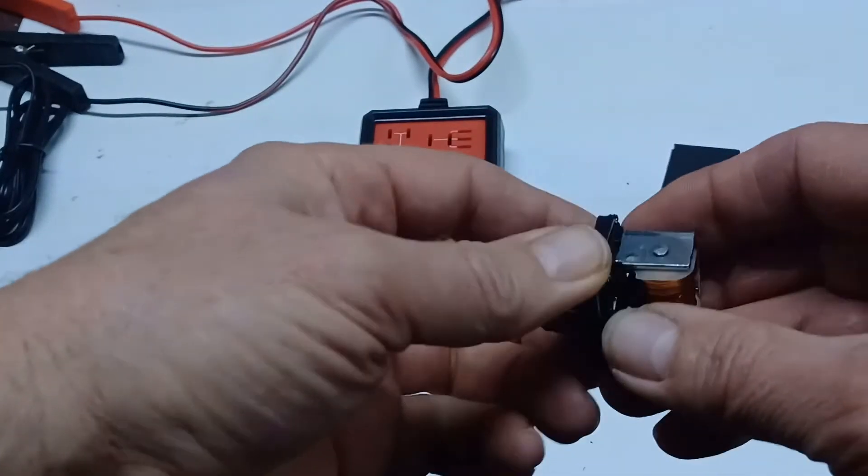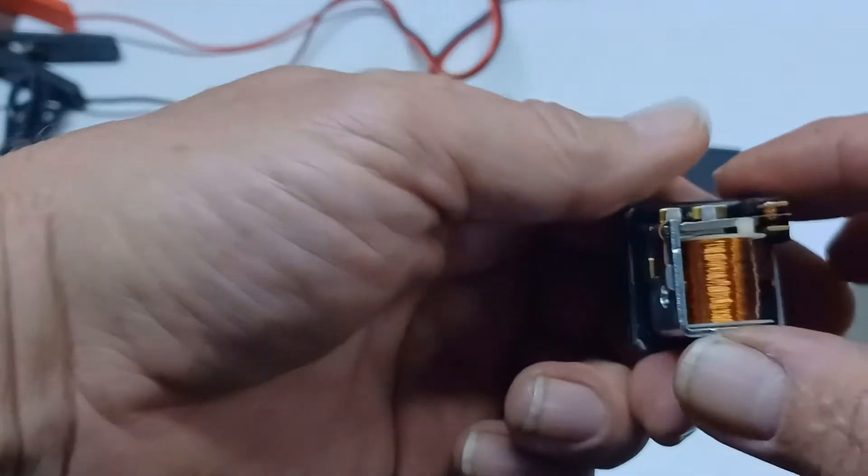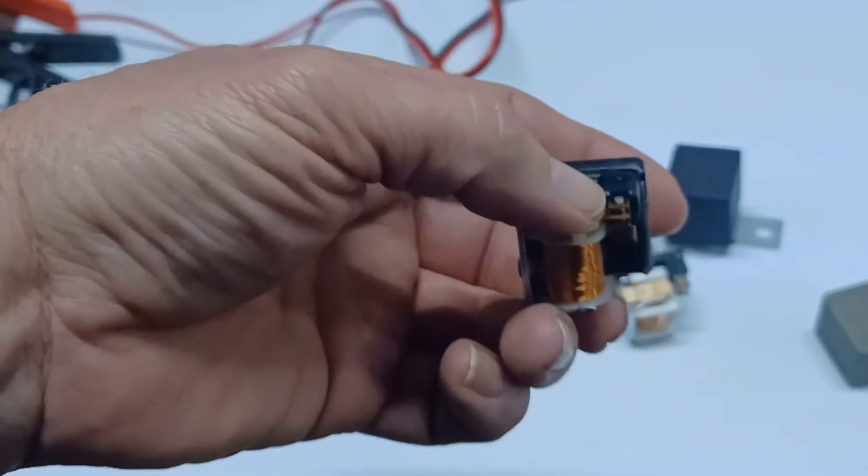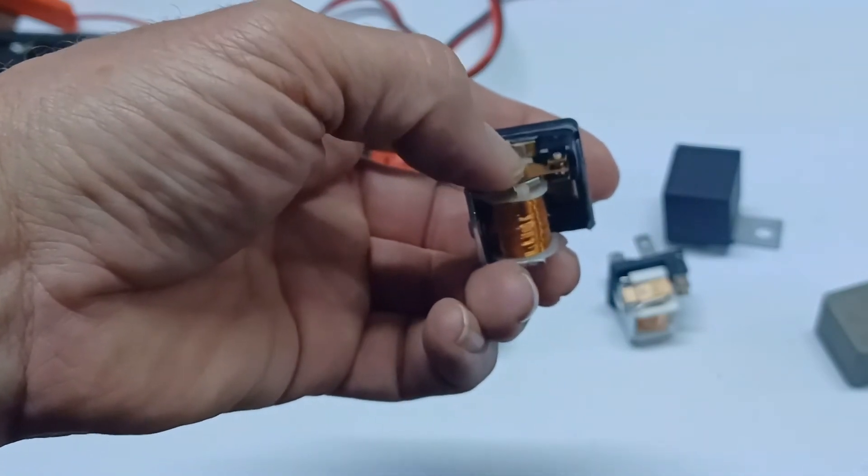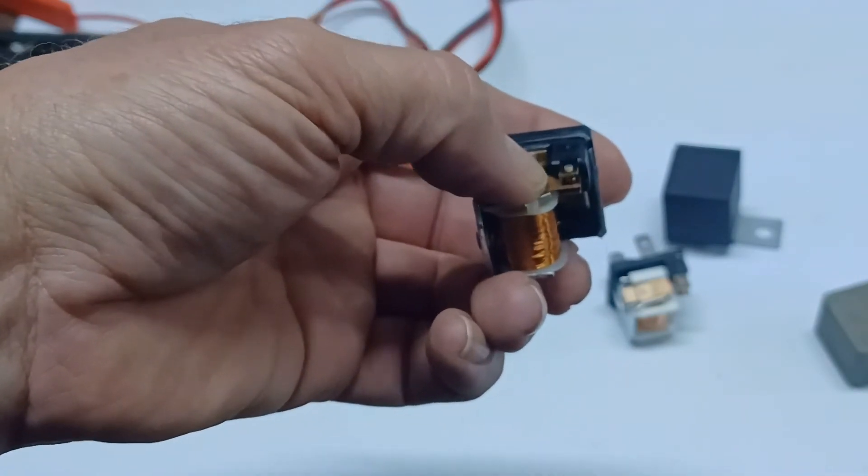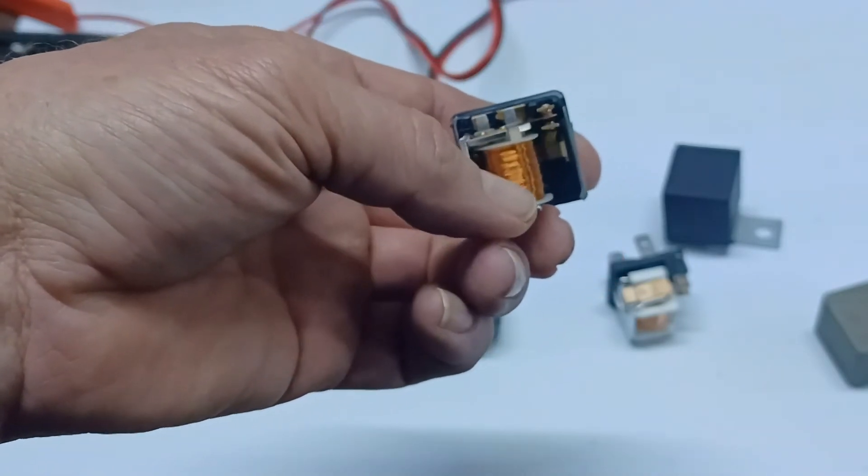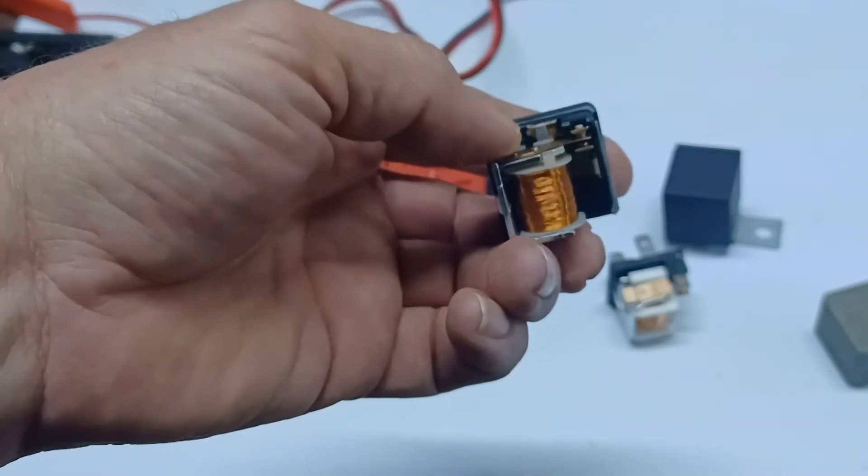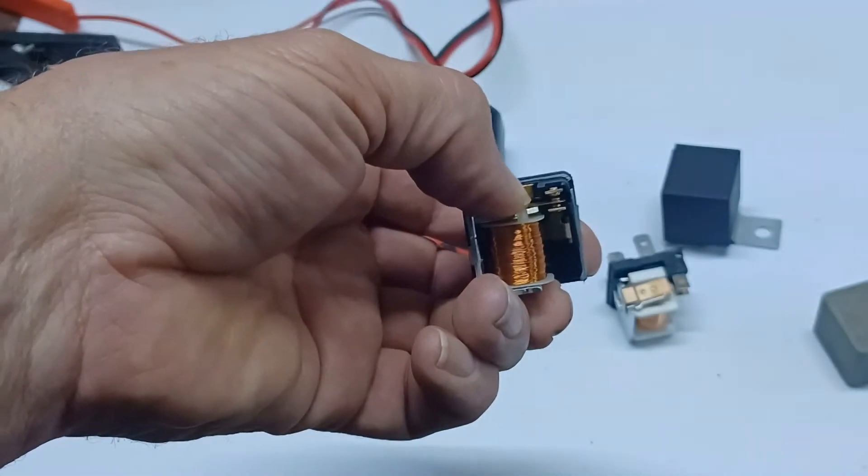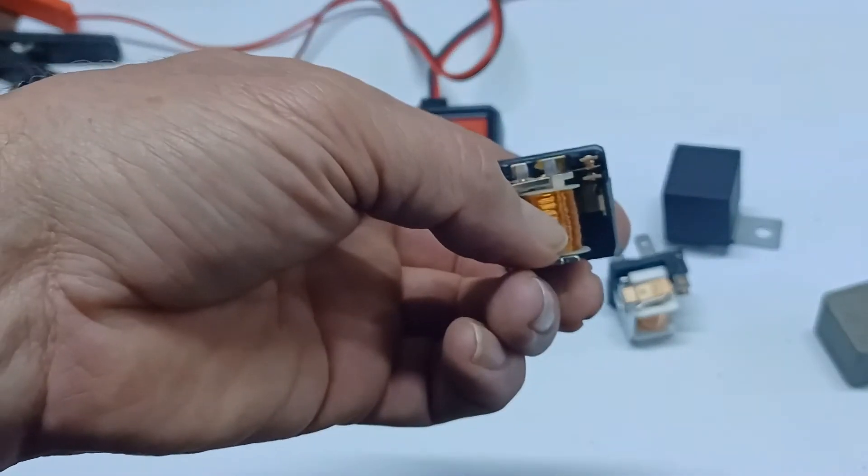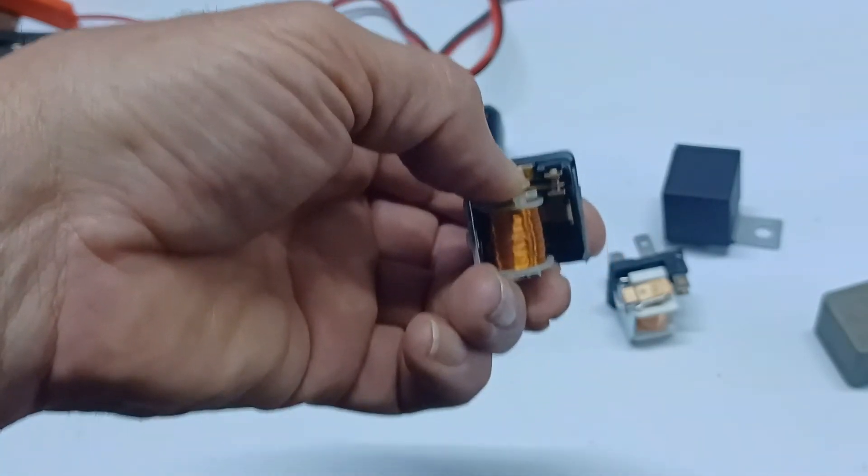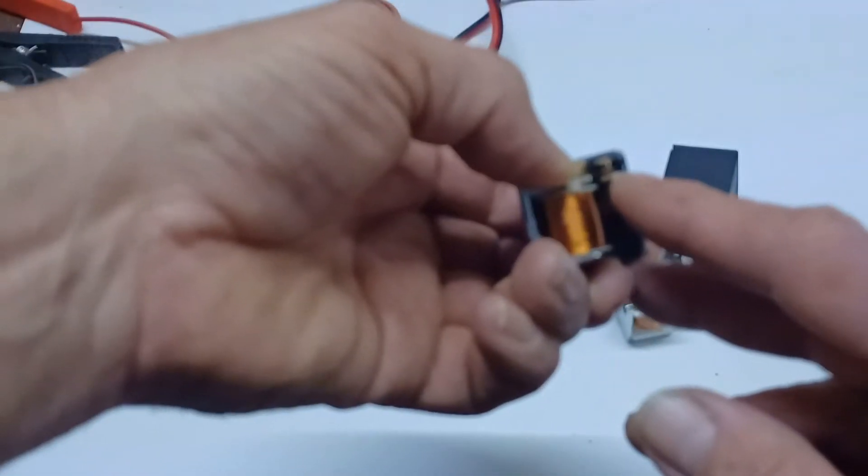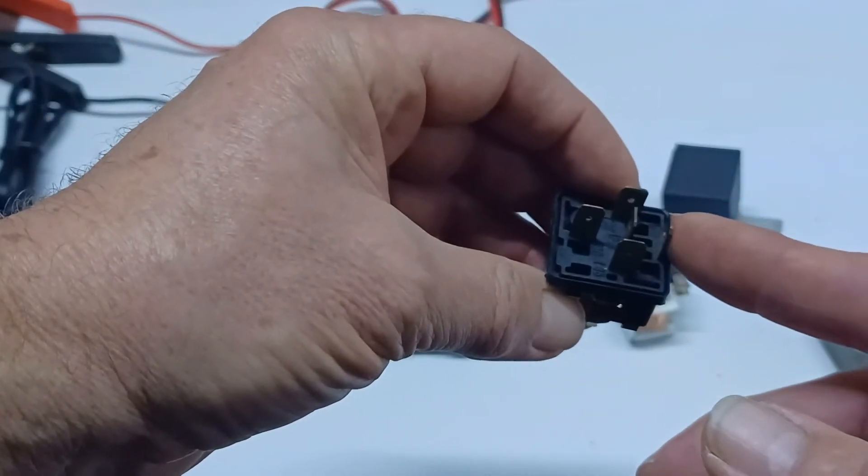So there's our Bosch and, let's get it around here. So there's the, you have to focus. There's our contact that's missing on the other one. So this is an electromagnet right here. And that's what pulls this down and makes the contact when electricity is applied to the magnet and then it pulls that down and makes contact across here, which comes out through this terminal right here.